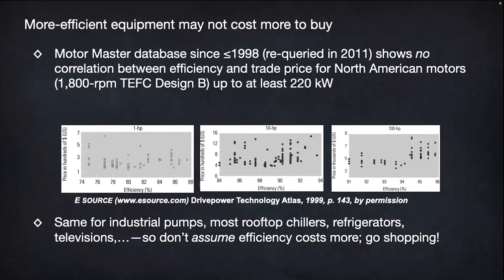As shown in the earlier right-hand graph here for 100 horsepower, around 1998, you could still buy the most efficient 100 horse induction motor, standard type, cheaper than nearly the least efficient, otherwise comparable specs—and therefore you could save a present value upwards of $20,000 per motor.